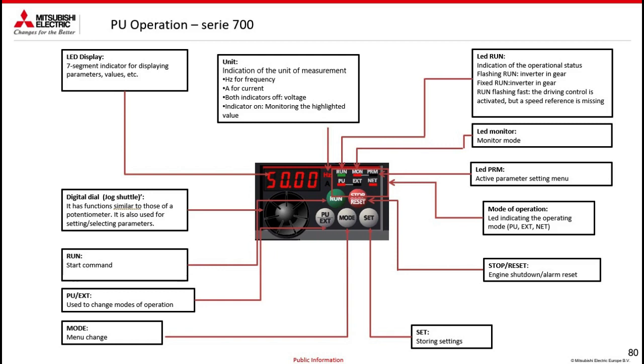And from here it will allow you to do the parameterization. MODE is the button with which you can enter the parameterization area. In fact, if you turn on the inverter and press the MODE button, you will read P0, so parameter 0. Then with the dial you go to look for the parameter you want. With SET you enter the parameter, you vary its value always with the dial, and then confirm the value you want with SET again.